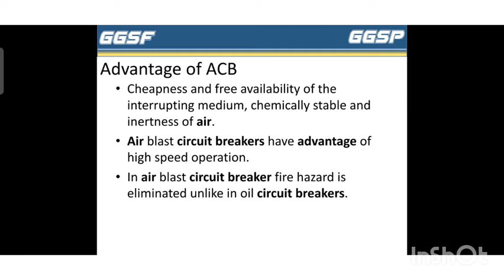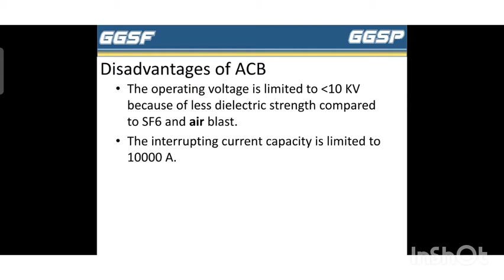Disadvantages of air circuit breaker: first, the operating voltage is limited up to 10 kilovolt because of less dielectric strength compared to SF6 and air blast. Second one is the interrupting current capacity is limited to 10,000 ampere.